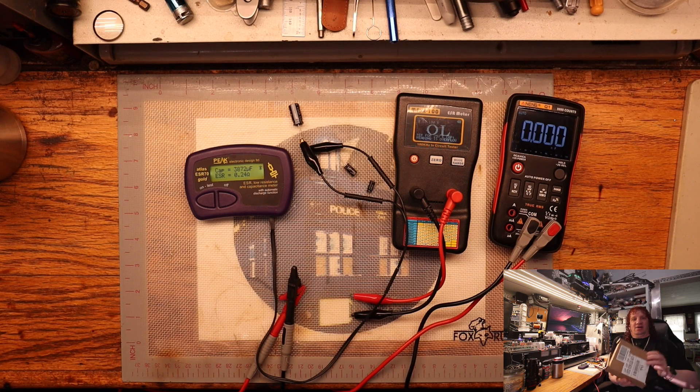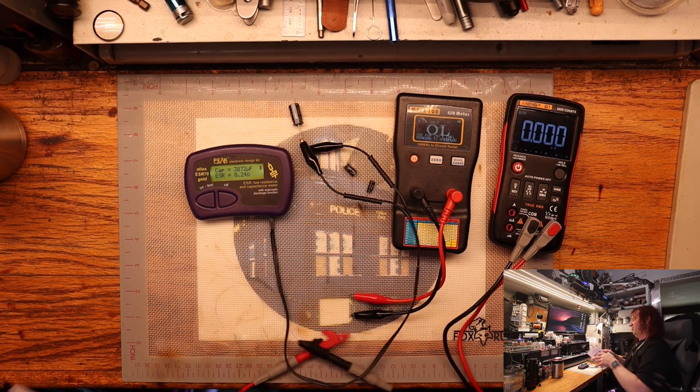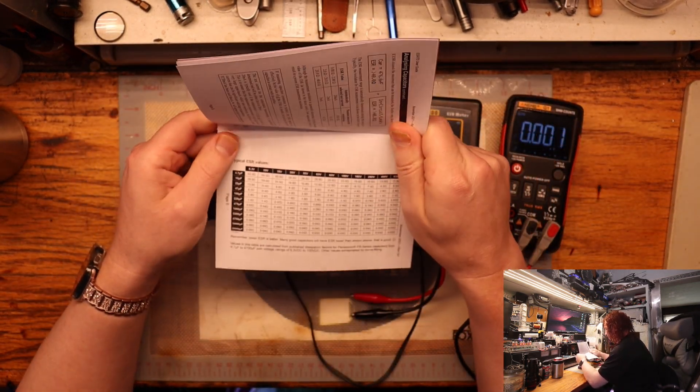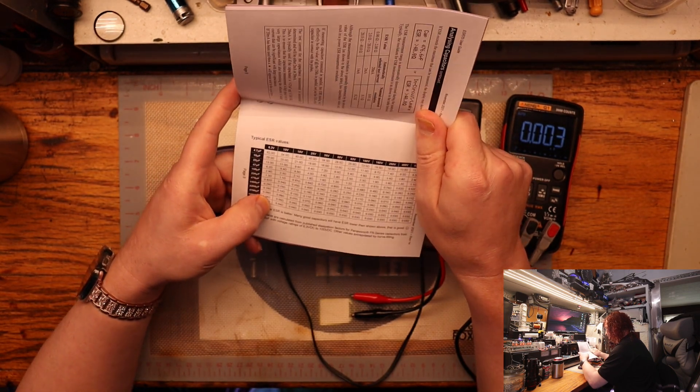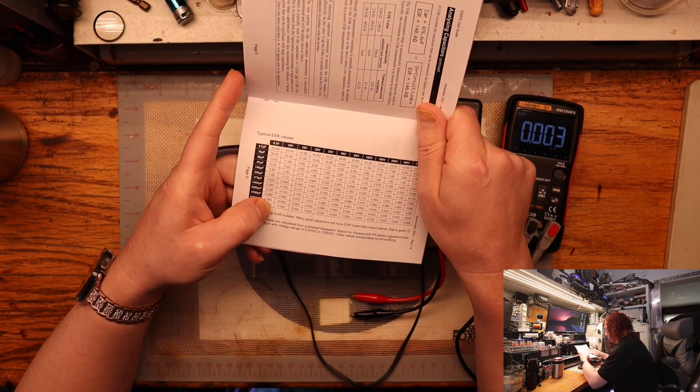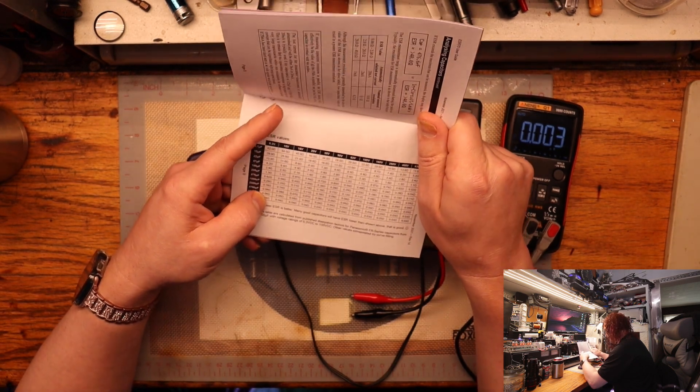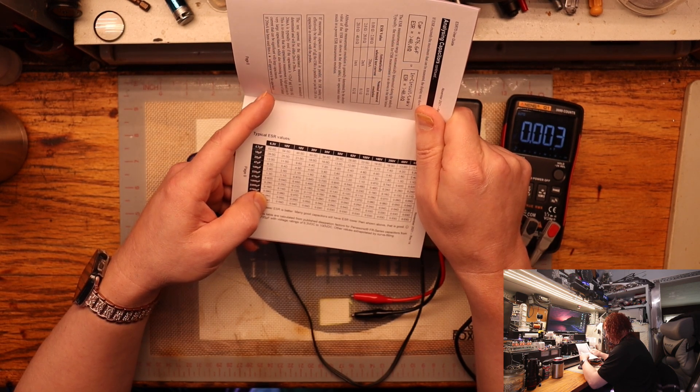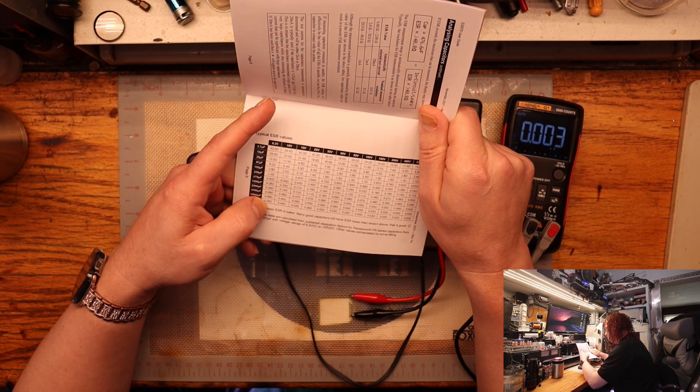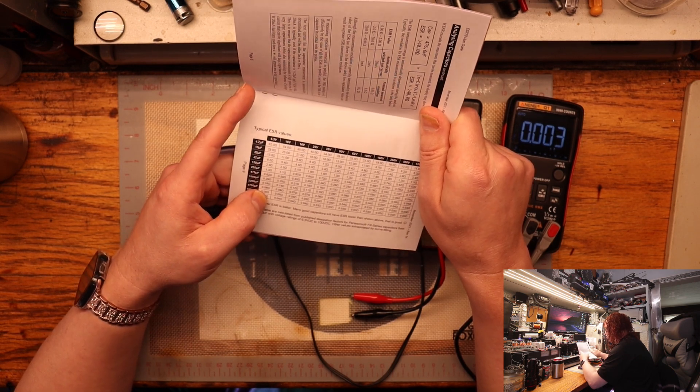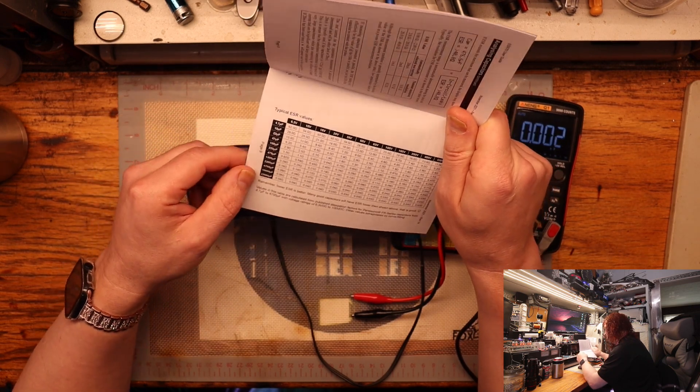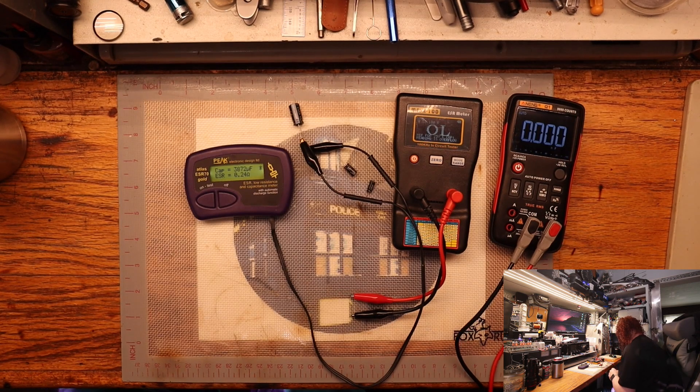The instruction manual actually gives you a chart. So we got 4.7 at 5.5 volts. If you work at 4.7, it should have resistance anywhere of 0.9 at worst case scenario. Of course if it doesn't come up on a chart then you have to do a best guess and fill in the blanks.